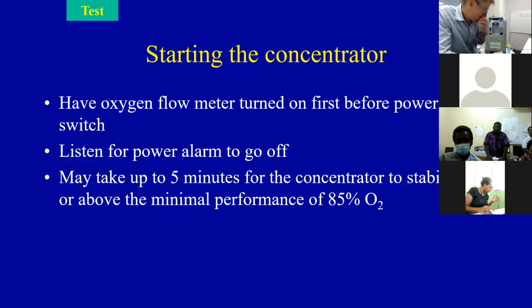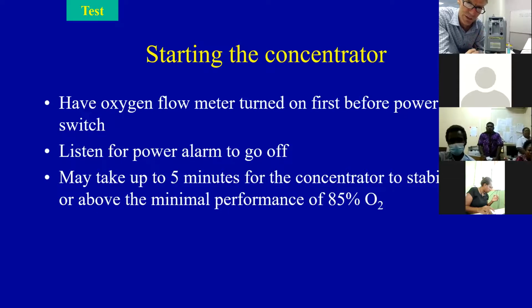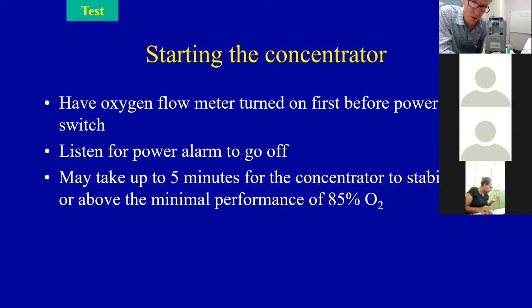The second thing is that before you start a concentrator, this is very important. Before you start the concentrator, you have to have the flow meter turned on. Did you notice that on this one, the flow meter is turned on? Now, the reason to have the flow meter turned on is so that the concentrator doesn't start working against an obstruction, and the obstruction would be if you don't have flow coming out here. So if you've got the flow meter turned off, then the power inside the machine is actually pushing against an obstruction, and that can damage the machine. So the simple thing is teach people to turn the flow meter on first before you turn the power switch on.